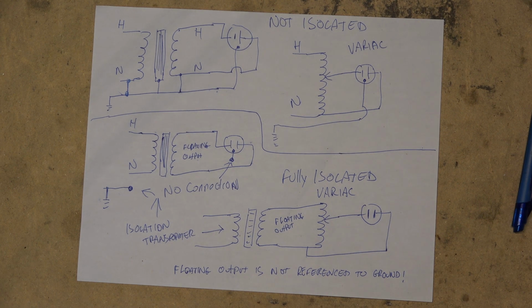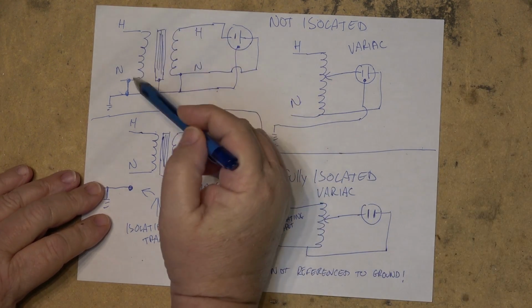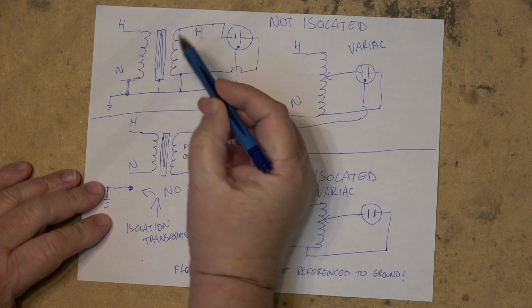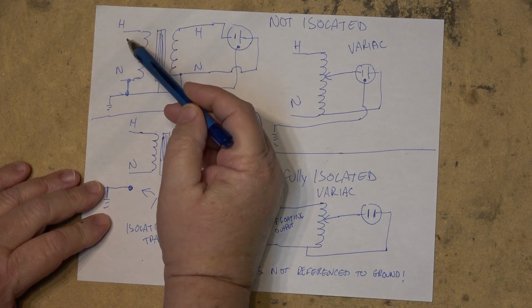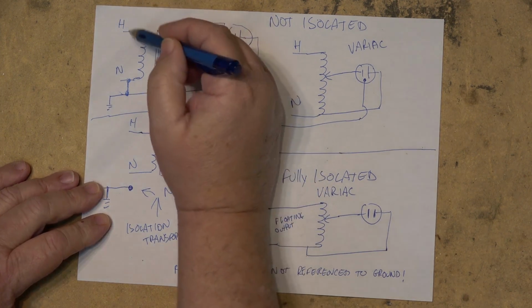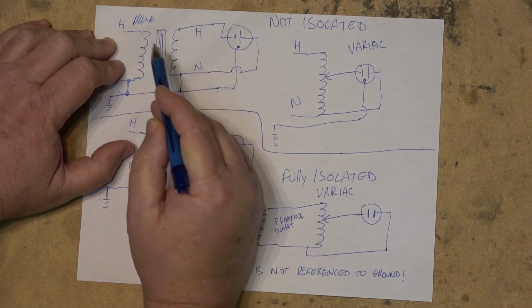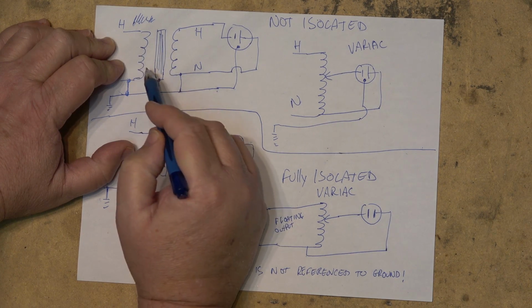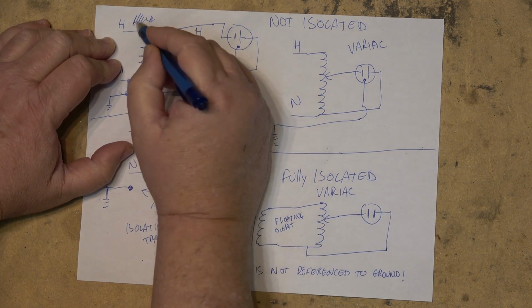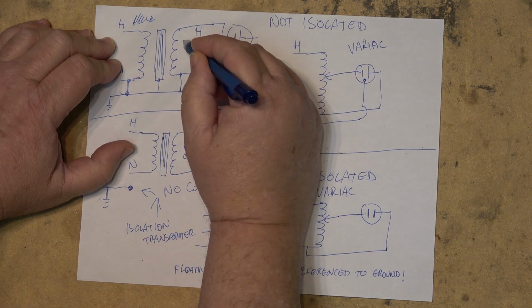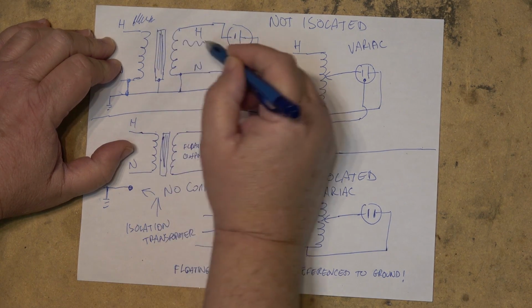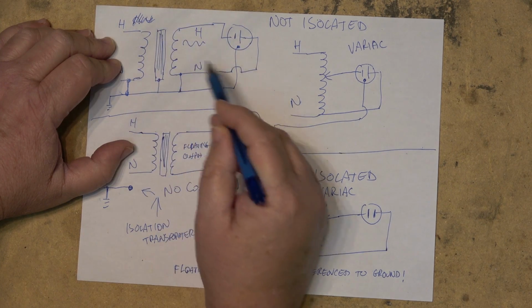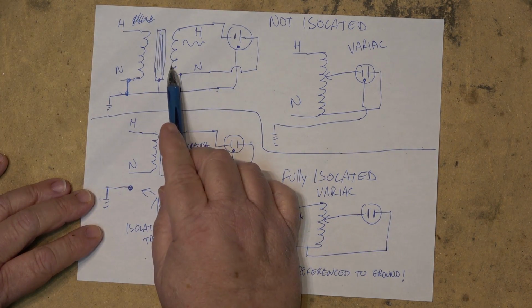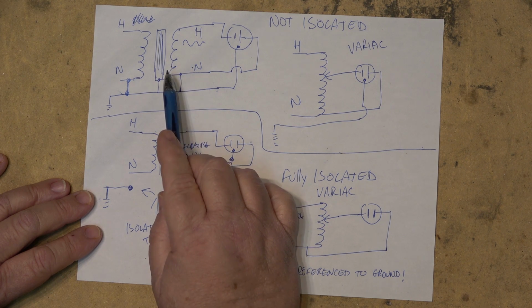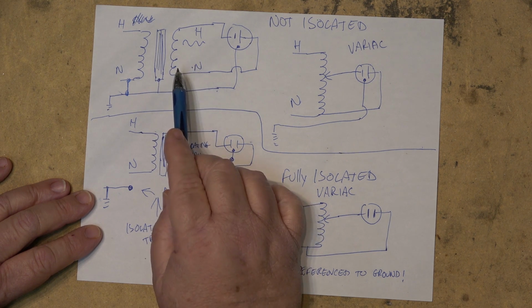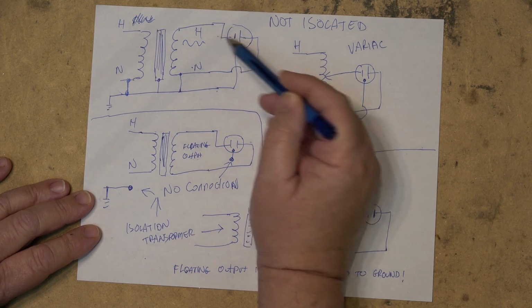The principle behind them is you've got your nice AC waveform coming through, which is being coupled through the magnetic core of the transformer, but any high frequency noise, any RF or any transients that's getting in here, any garbage that's getting in here higher than the resonant frequency of the transformer is not going to make it. So you could have your sine wave with a bunch of garbage on here, and what's going to come out here is a nice clean sine wave instead of a sine wave with all kinds of garbage on it. That's what these do. They do not protect you in any way, shape or form whatsoever, because they still have a hot and a neutral.